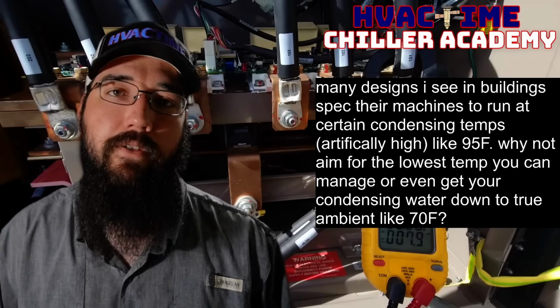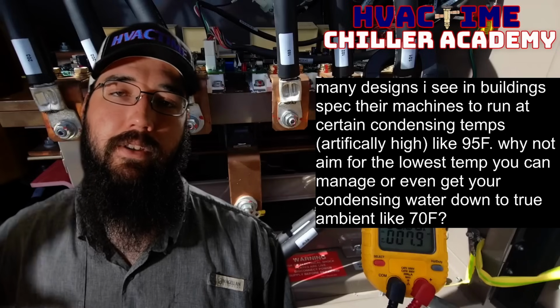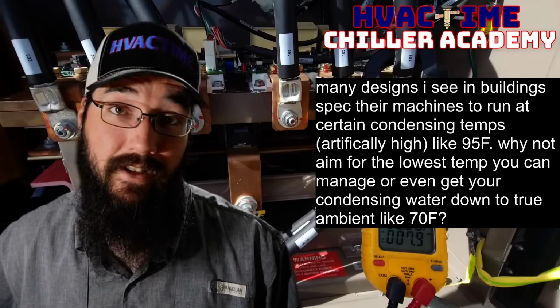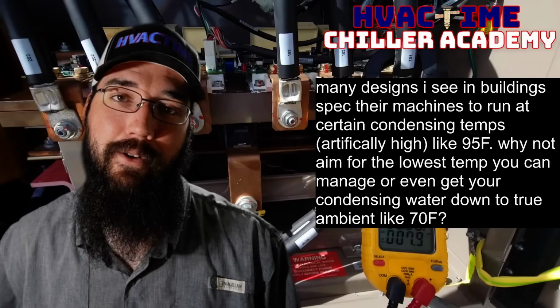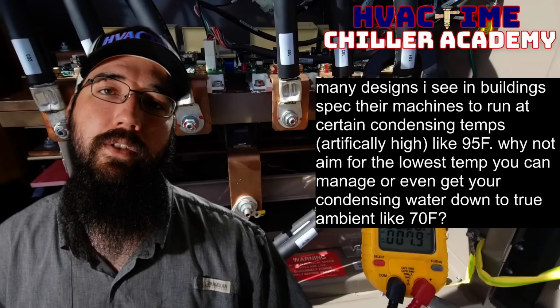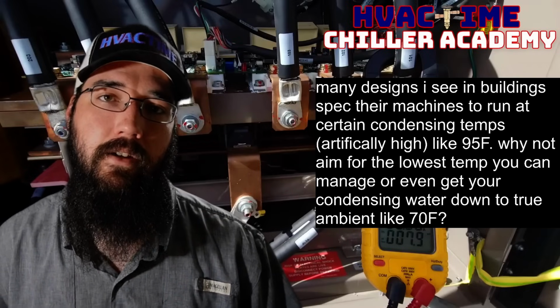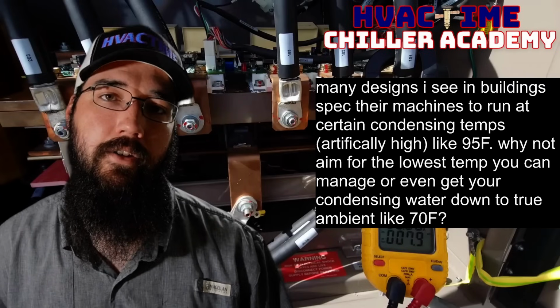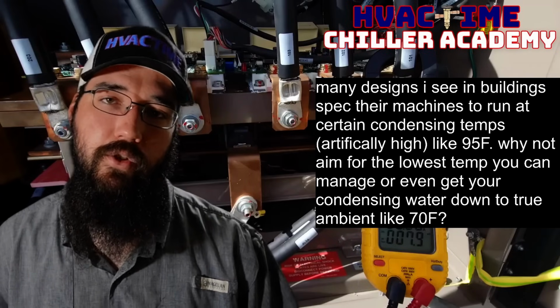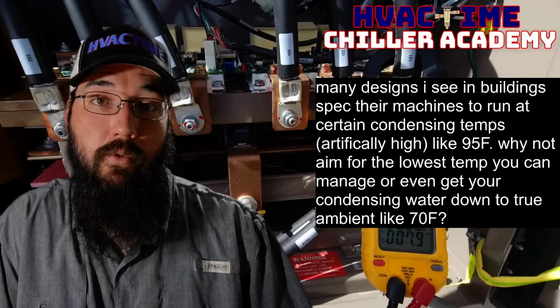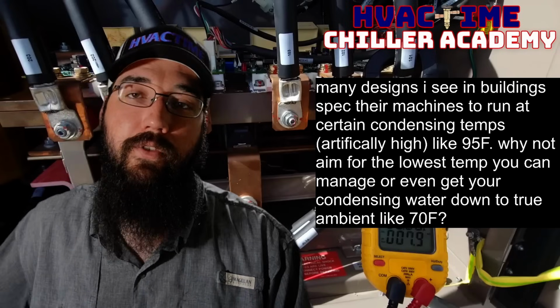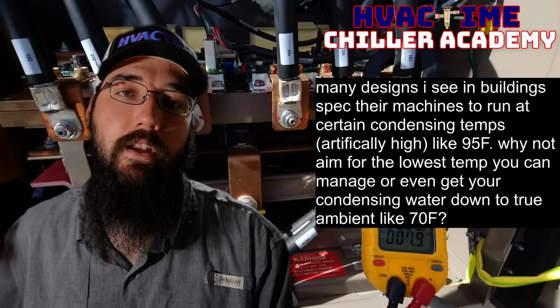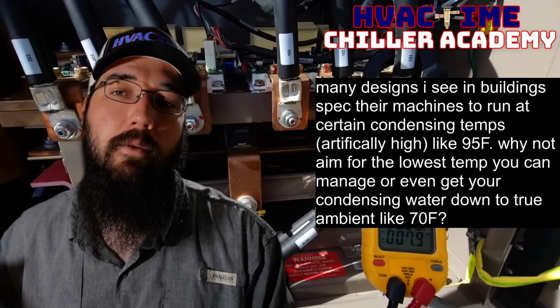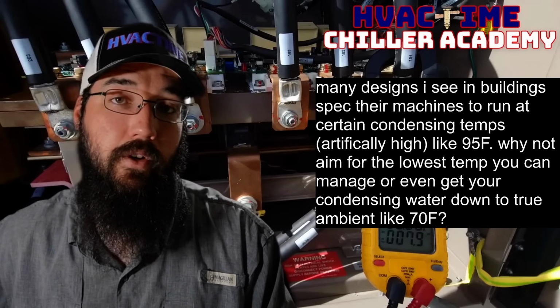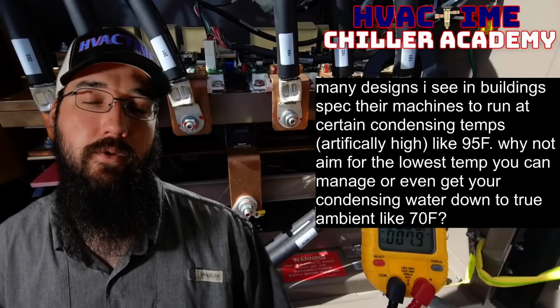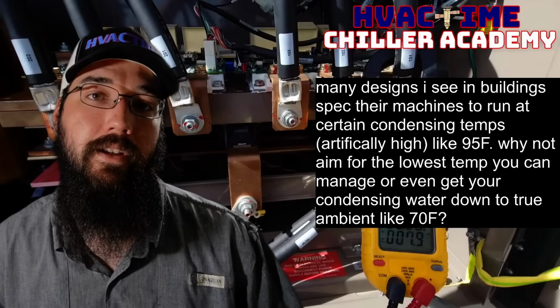It is way more efficient to put the extra load on the tower fan, and it's a hell of a lot easier to fix a tower fan motor than to try to service a chiller that's been beat to hell because we're trying to run high condenser waters. Whether it be a surging issue, that would be the worst case scenario, right? You're artificially trying to use less energy in your cooling towers by raising the condenser water set points, but now you've pushed your chiller to a point where it's more frequently surging.